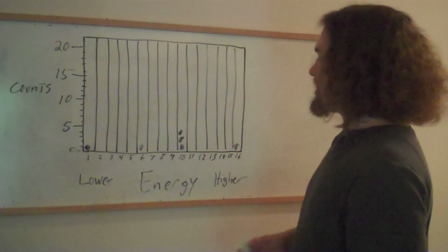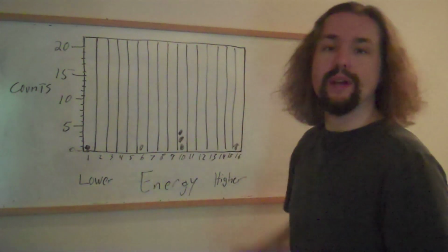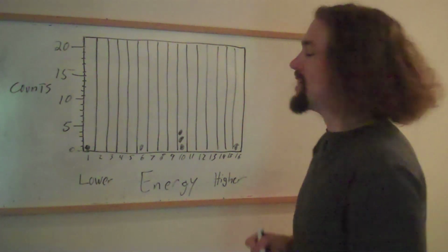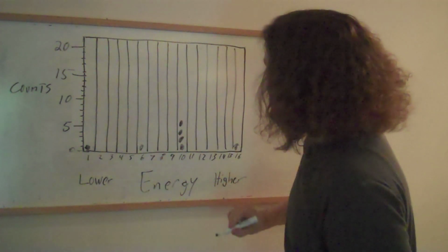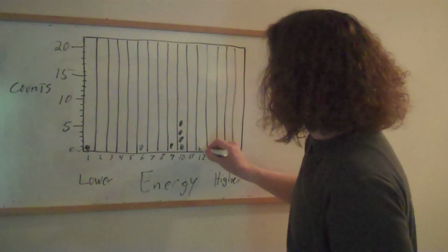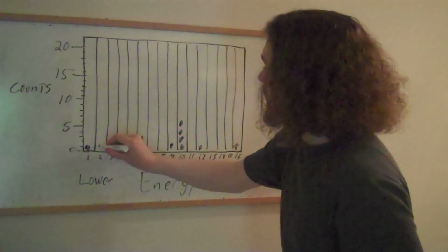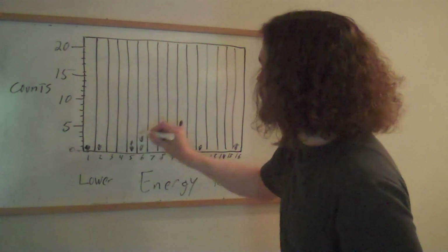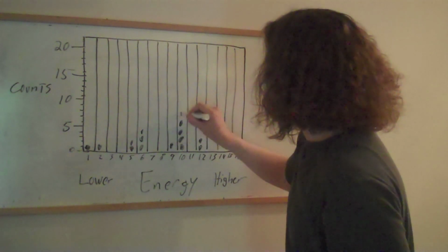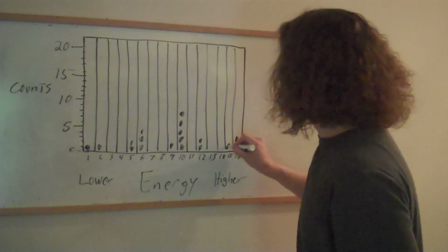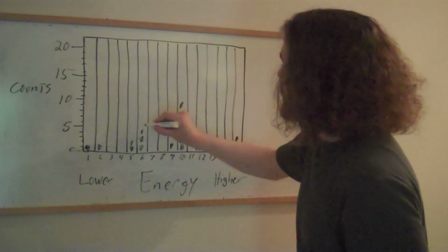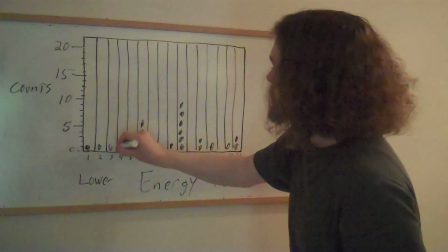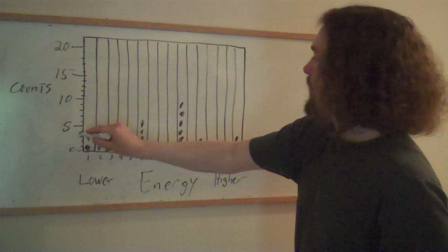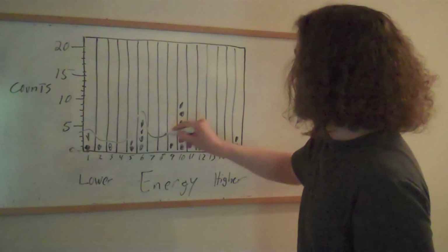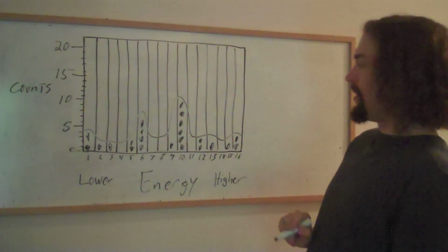And so that 661.66 is somewhere over here when it comes through, the one for cesium-137. And as these little tiny photons appear, they'll be all over the place. And they'll start to stack up as they're counted and counted and counted. And this counting process can take hours and days, depending on how they show up. But as it starts to happen, you start to get a pattern. See that pattern?